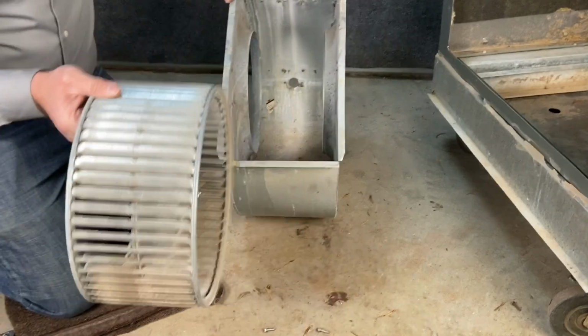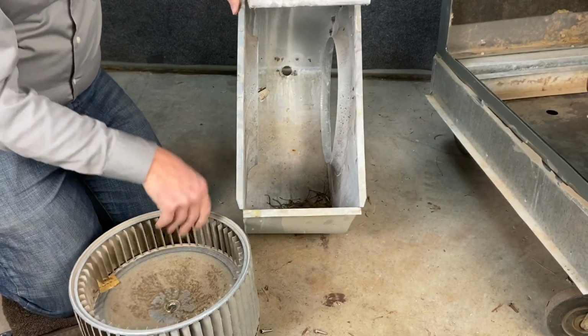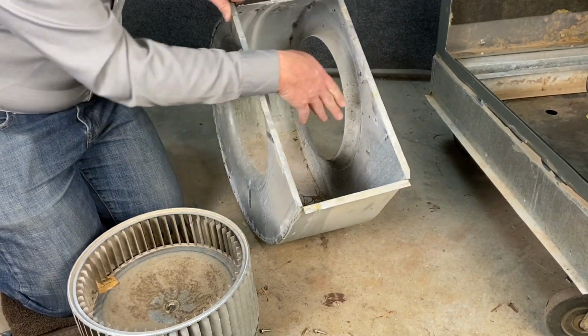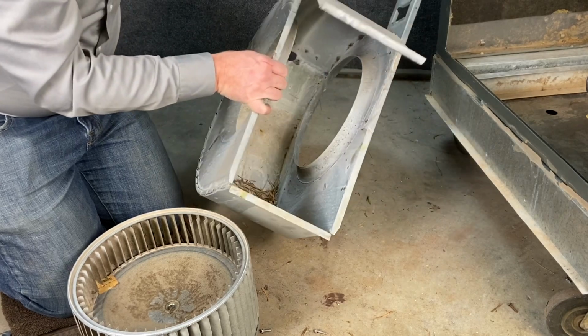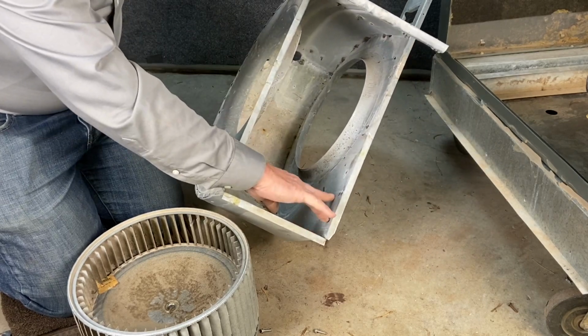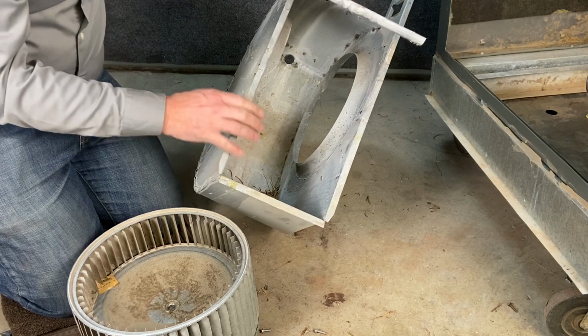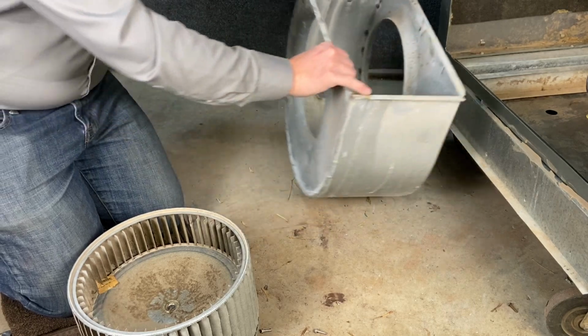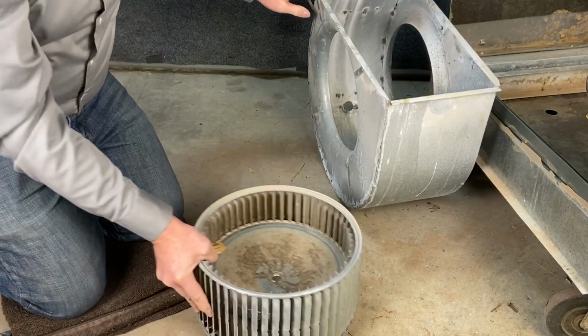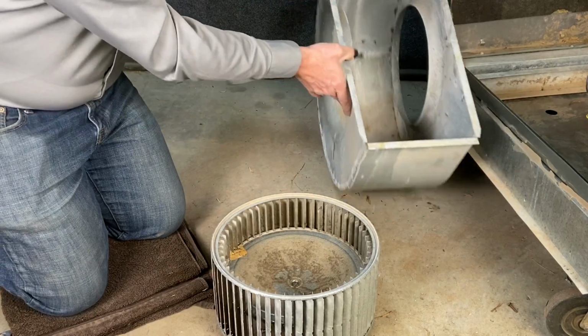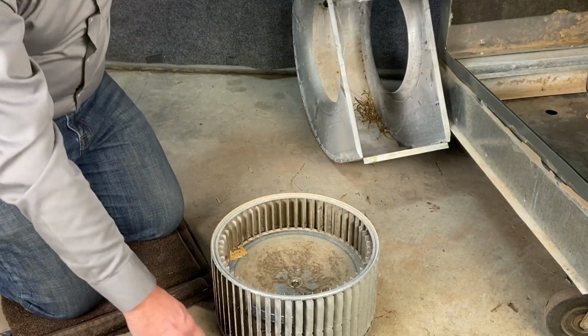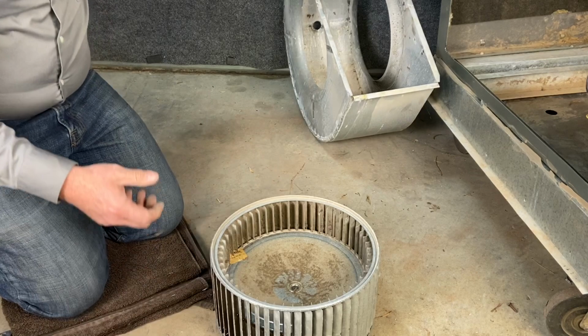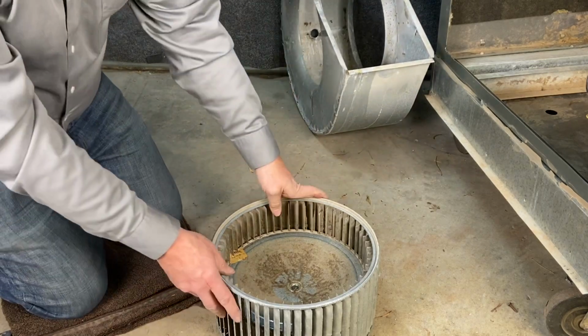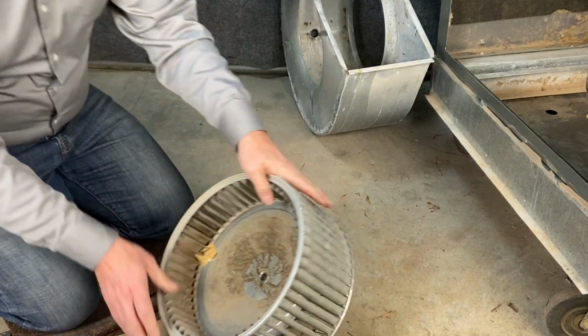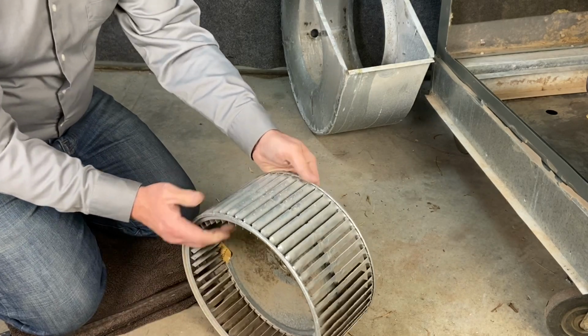If I pull this out, we can see that there's all kinds of dirt in here. I also see a little bit of stains here on the side. I can tell this has been washed before. Somebody used some kind of a chemical on this once before, but it needs to be washed again. This is our blower wheel. A lot of people call them a squirrel cage housing or a squirrel cage, hamster wheel, squirrel cage wheel, all these different words that we use, but it still means the same thing. This is the blower wheel.